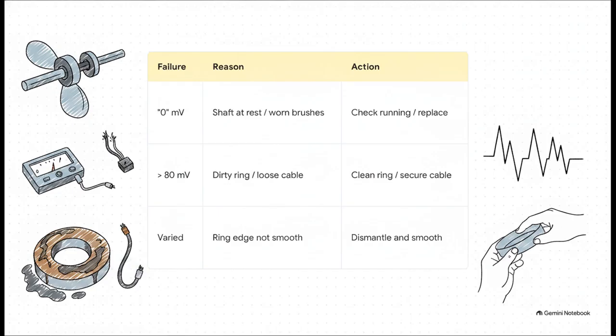But if you're out sailing and you read 0, your cables might be shorted, or your brushes are totally worn out and need replacing. If the reading is too high, above 80, you almost certainly have a dirty slip ring covered in oil or rust, or maybe a loose earthing cable. And if the millivolt value is just jumping around and varying widely, the edge of the slip ring probably isn't smooth anymore. The fix there is to dismantle it, remove any gap, and rub it perfectly smooth with emery paper.